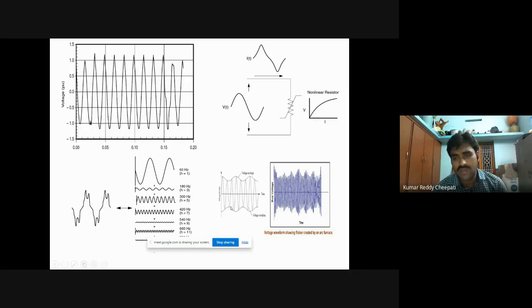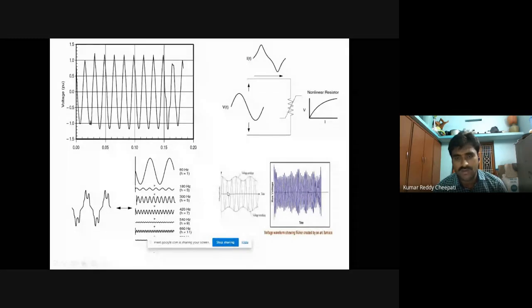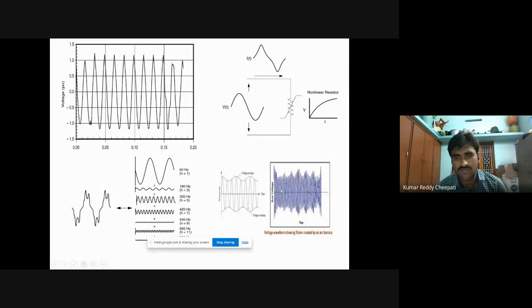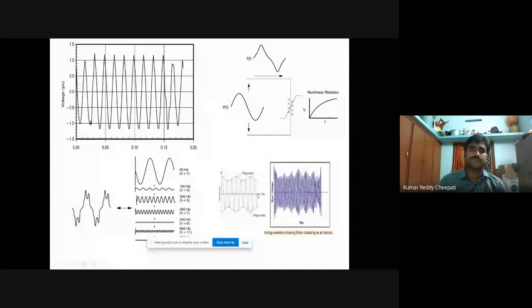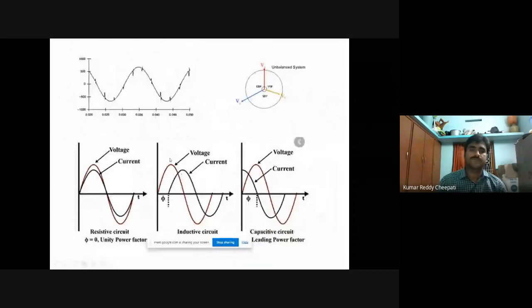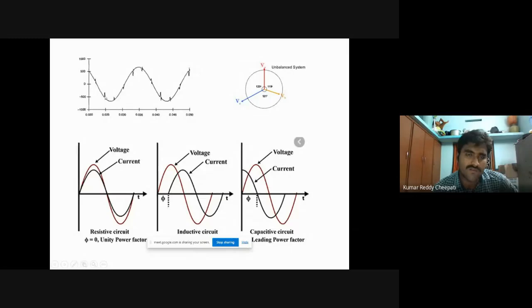This is the diagrammatic indication of notching, where we get different amplitudes of the waveform periodically. That is called voltage notching. And this is the diagrammatic indication of voltage flicker, which is generated by the arc furnace. This is also a diagrammatic indication of the voltage flicker, which is due to the arc furnace.